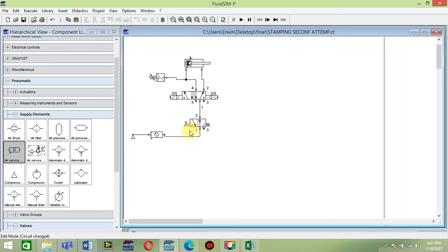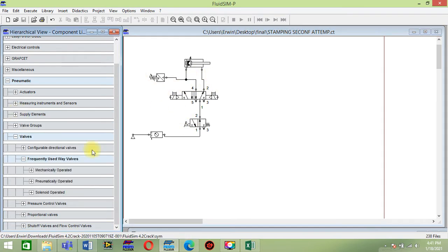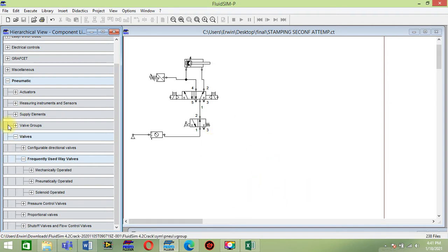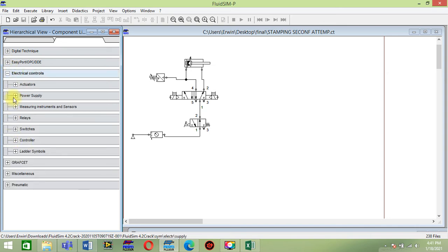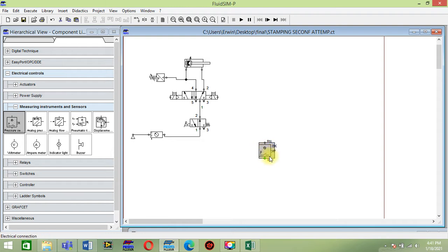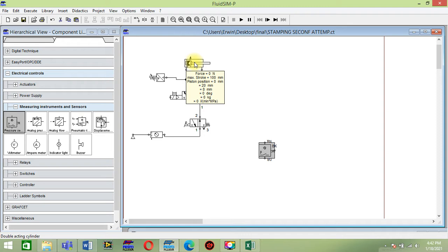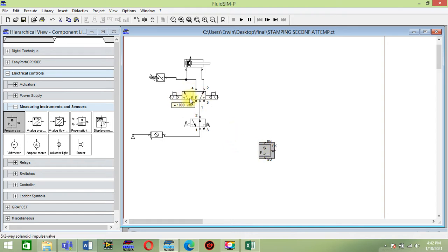For the electrical circuit, go to electrical control, then sensor, and first put pressure sensor. This sensor will serve as the switch of this cylinder. When the cylinder reaches the limit of the desired pressure for stamping, this sensor will make a signal to activate this solenoid so that this flow will activate.